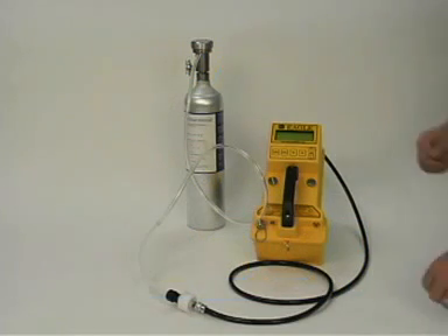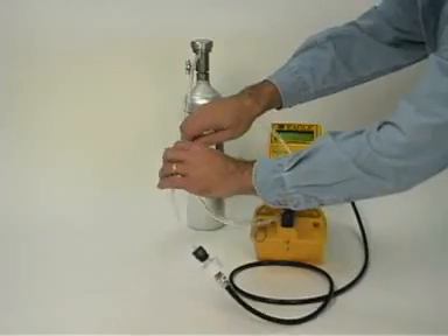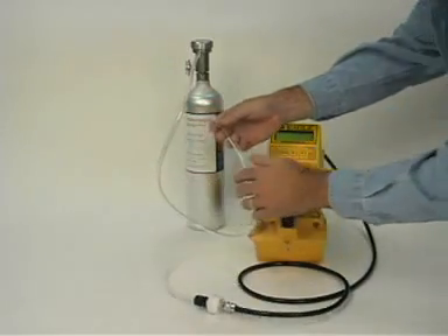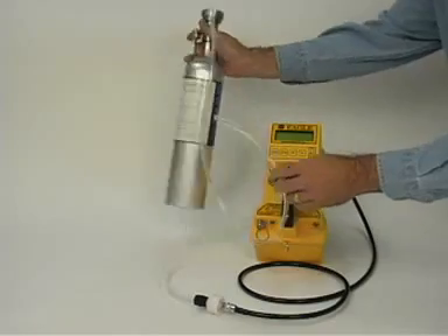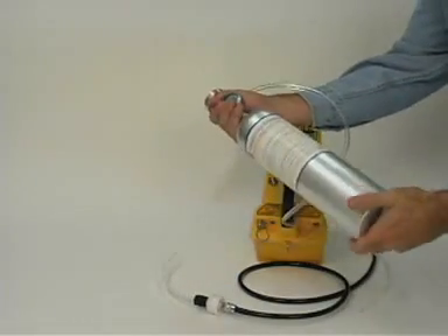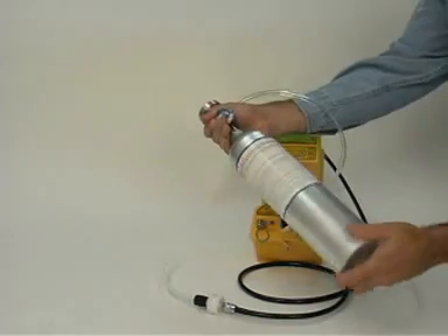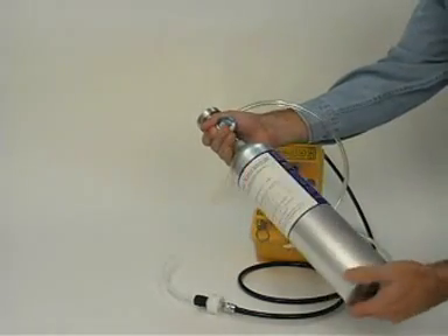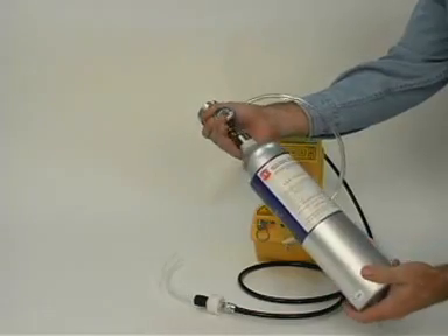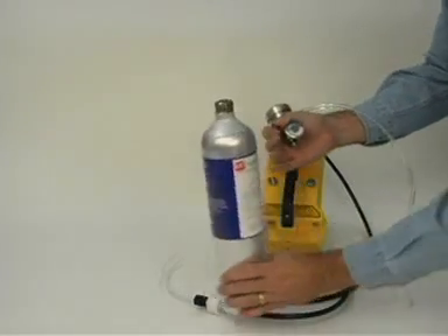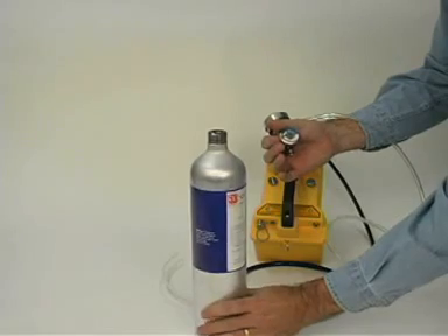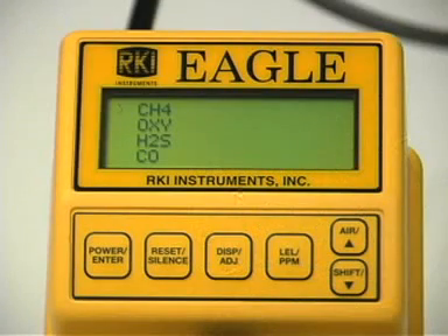Next, disconnect the tubing from the probe. Unscrew the calibration cylinder from the regulator. Repeat this procedure for any other channels you want to calibrate. Make sure you use an appropriate calibration cylinder for each channel.